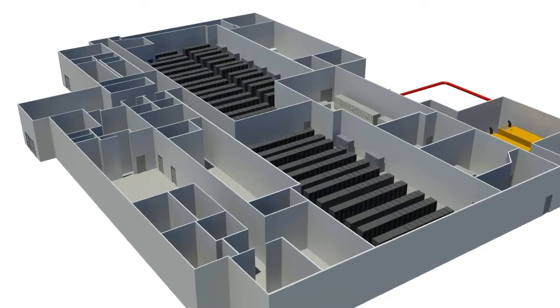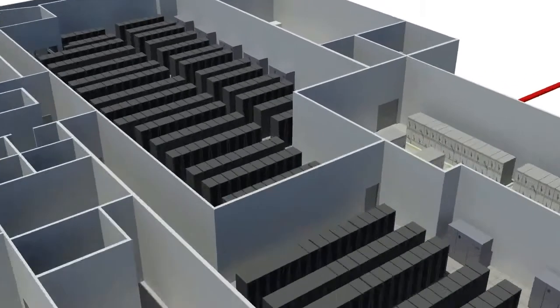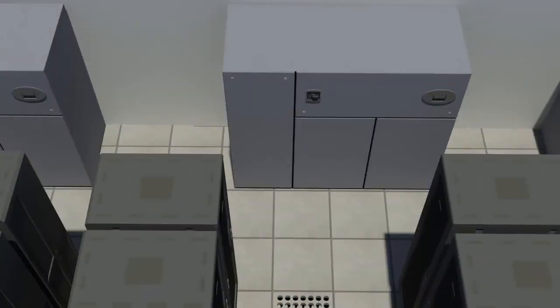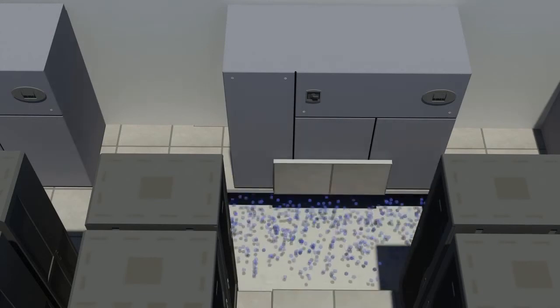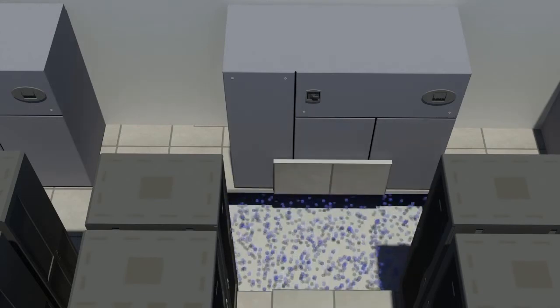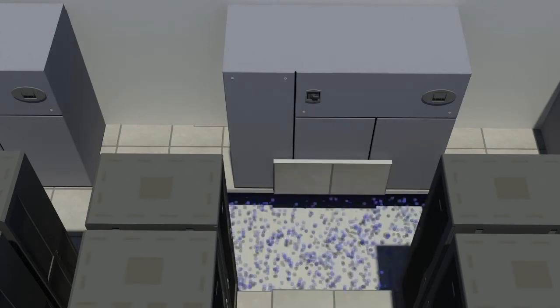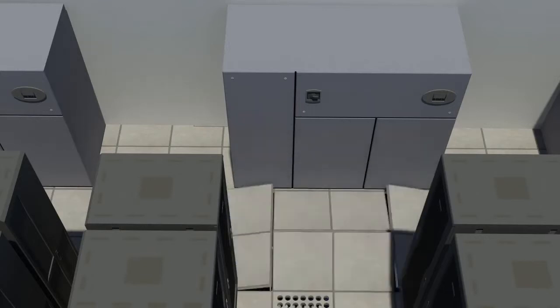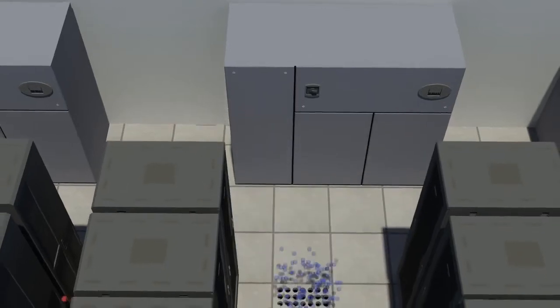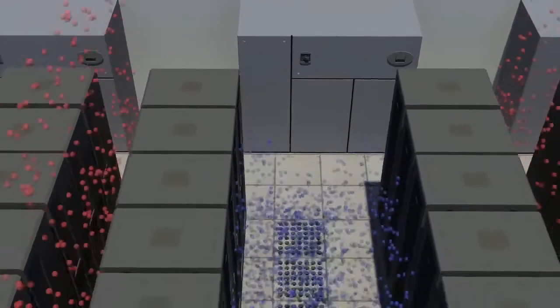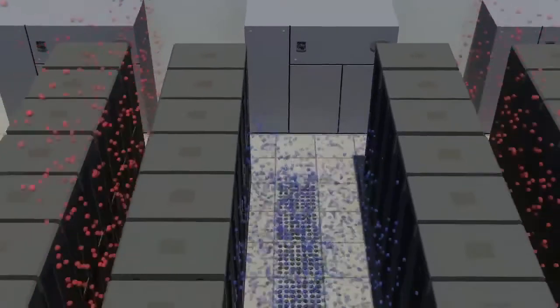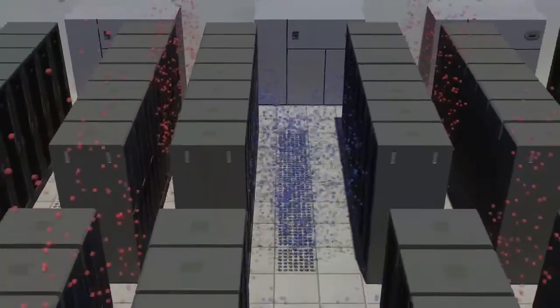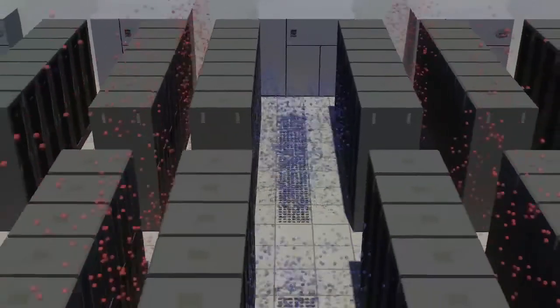Cold air molecules are pushed from the computer room air conditioner unit under the floor, creating a high-pressure system that forces the chilled air up through air vents in the cold aisles. That chilled air is pulled in through the front of the server cabinets and then fanned back out as hot air in a hot aisle.